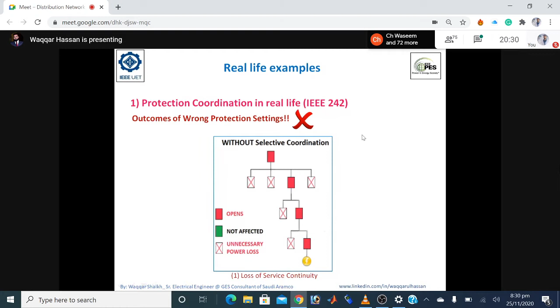The second type of loss can be damage to the electrical equipment. Now you can think of a scenario where your protection devices are given wrong settings and they do not trip at the right time. So the fault may damage the bus bars or the assemblies from where the power is being distributed. This is an example of a switchgear which is blasted or affected due to lack of tripping of the protection devices. Okay, so this is the second level of harm which can occur in your network if you are ignoring these types of studies and you are not giving the proper settings into your protection relays or circuit breakers.